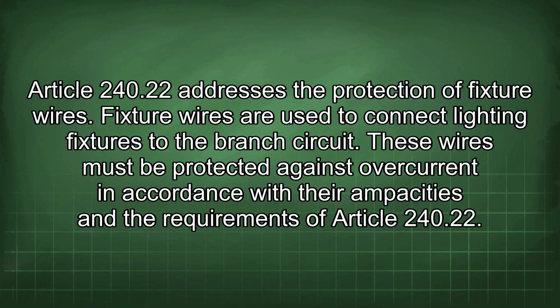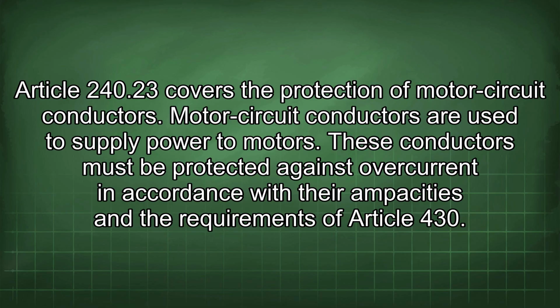These wires must be protected against overcurrent in accordance with their ampacities and the requirements of Article 240.22. Article 240.23 covers the protection of motor circuit conductors. Motor circuit conductors are used to supply power to motors. These conductors must be protected against overcurrent in accordance with their ampacities and the requirements of Article 430.